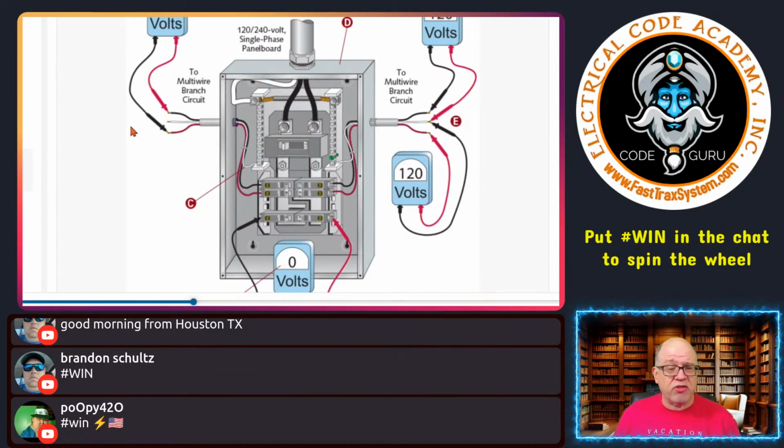Now, what I'll talk about is just some little things to remember. If I happen to have a raceway coming in, and I have multiple circuits in here, multiple ungrounded conductors, and multiple neutrals coming in, then you have to make sure that you identify which set of ungrounded conductors this neutral goes with. This can be done with a simple tie wire.